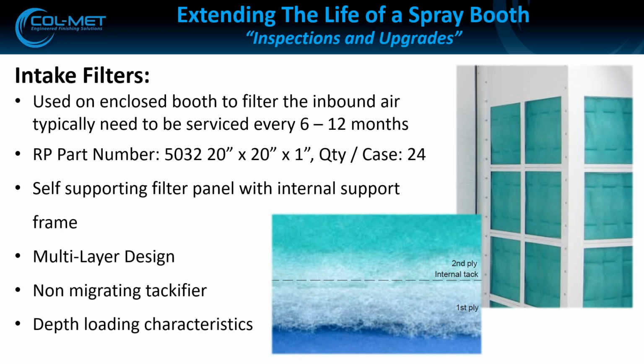The tack is there to catch the very small microns, the ones too small to carry enough inertia to impinge onto the filter media. They float through the air and through the filter, bouncing around because they're so small, and they may or may not get intercepted by the media. With intake filtration we're normally dealing with dry particulates, so we need something tacky that can reach out and grab them.